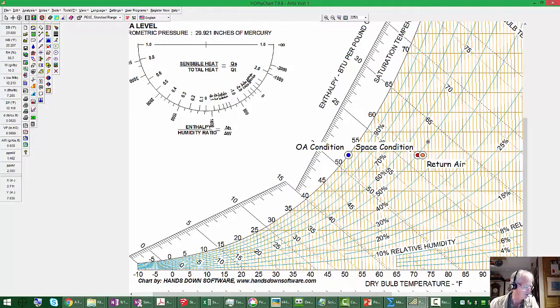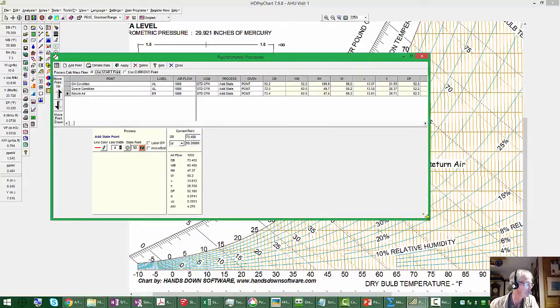You could open up our little table, and the symbol for enthalpy is H, and the enthalpy of the outdoor air is 21.55. The enthalpy of the return air is 26.71. So the return air has more energy in it than the outdoor air, so we would actually want to be on 100% outdoor air under the current condition, even though it's foggy outside.